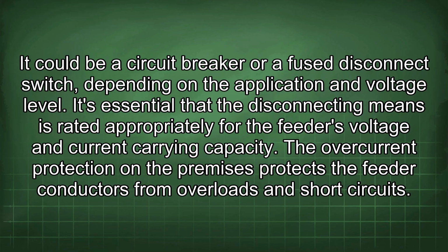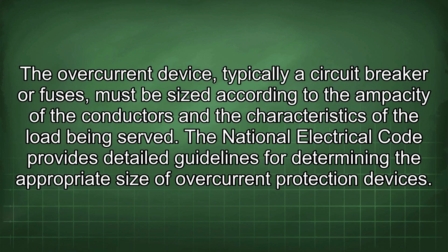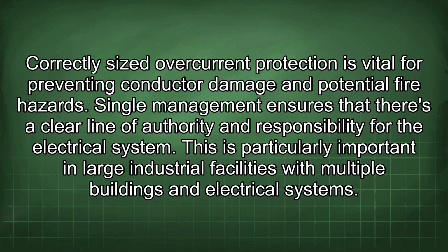The overcurrent protection on the premises protects the feeder conductors from overloads and short circuits. The overcurrent device, typically a circuit breaker or fuses, must be sized according to the ampacity of the conductors and the characteristics of the load being served. The National Electrical Code provides detailed guidelines for determining the appropriate size of overcurrent protection devices. Correctly sized overcurrent protection is vital for preventing conductor damage and potential fire hazards.